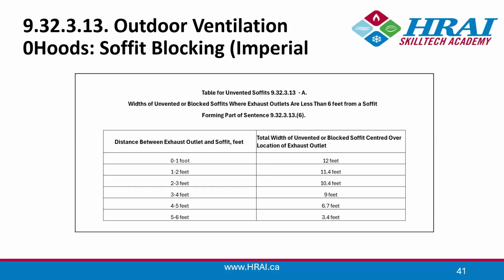So soffit blocking: when you have exhaust ducts in a soffit or close to a soffit, the soffit must be blocked so that the warm, moist air coming out of the exhaust duct doesn't just get drawn into the soffit, which you're trying to use to ventilate the attic, and cause problems there with mold, etc. This is one of those common sense things that we always knew, but it wasn't actually ever written into the code.